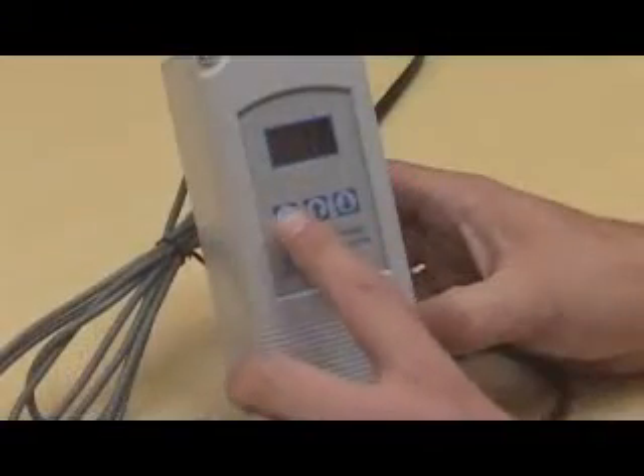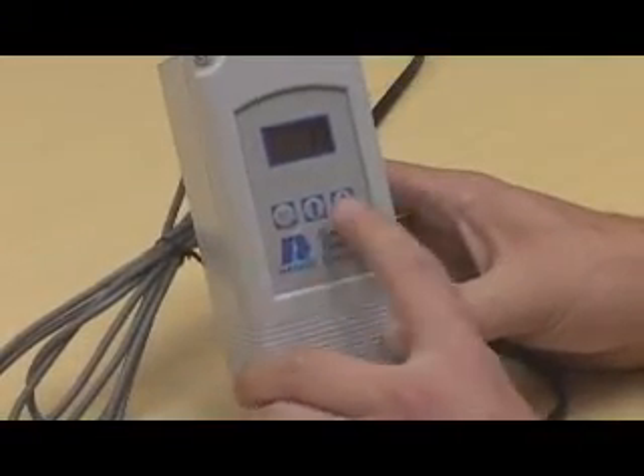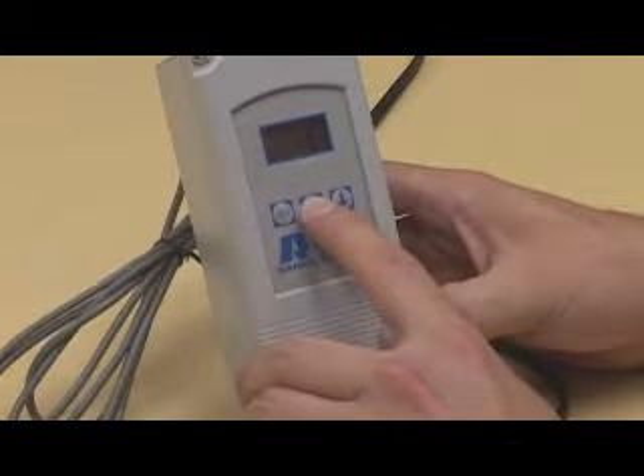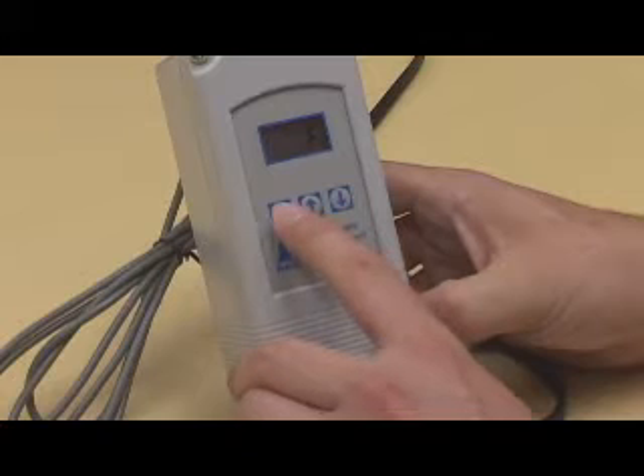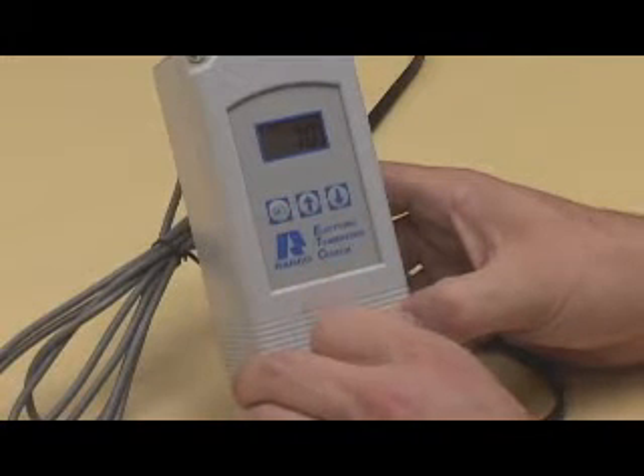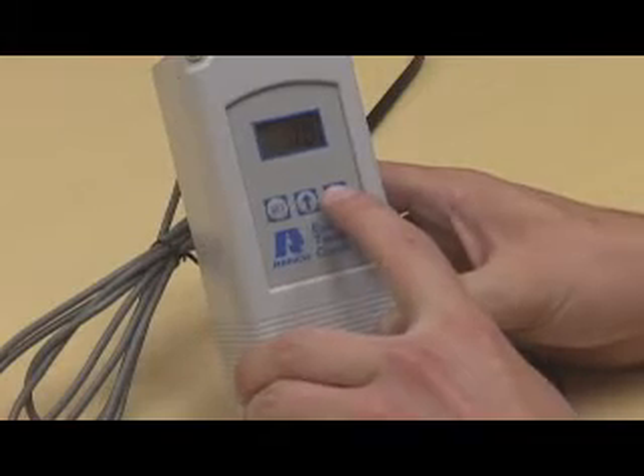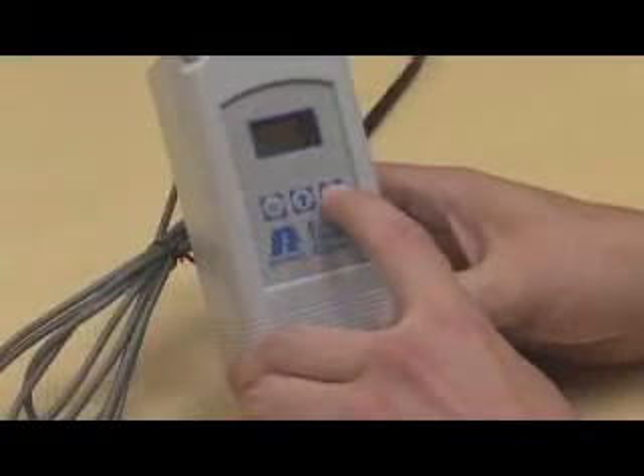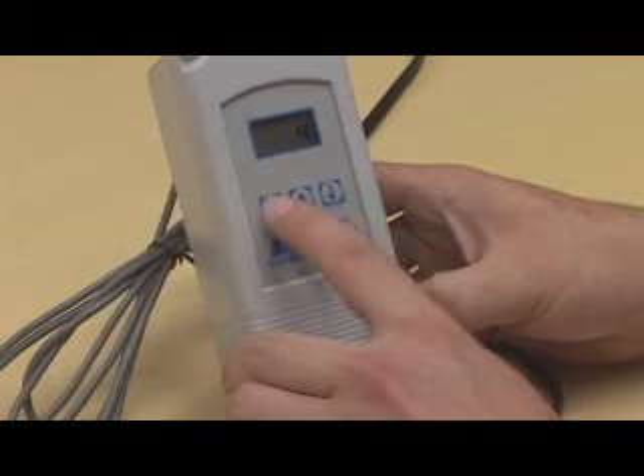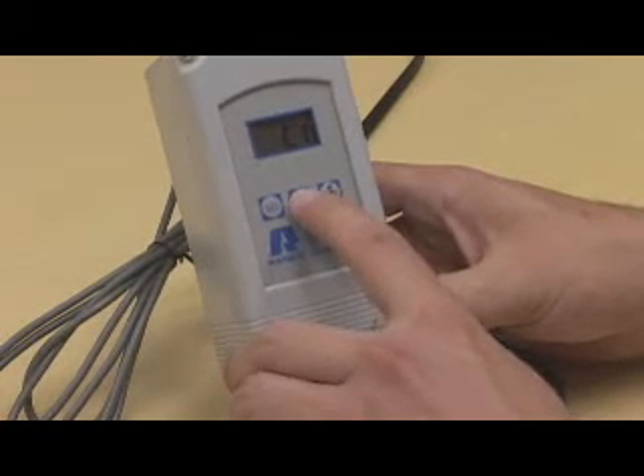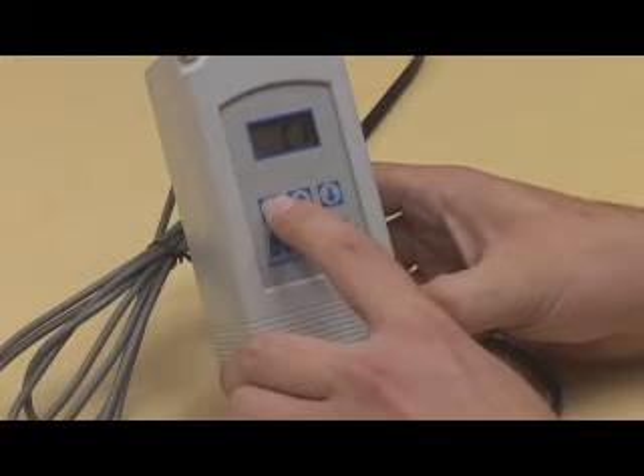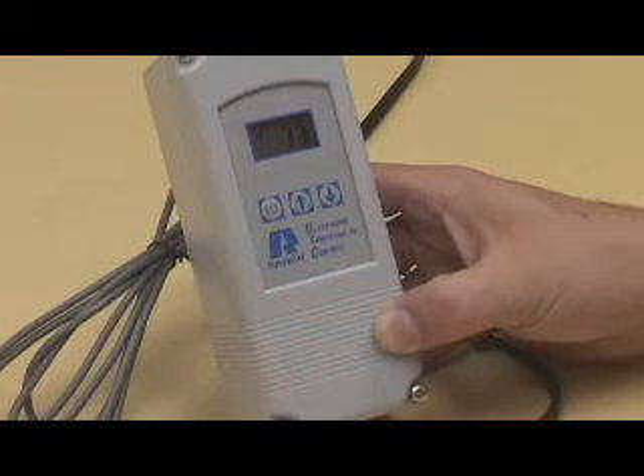Next, you are ready to program the unit. The ETC can be programmed in 4 simple steps using the 3 keys on the face of the control. 1. Press the set key once. Select F for Fahrenheit or C for Celsius using the up and down arrows. 2. The LCD display will show set point S1. Use the arrows to select set point. 3. The LCD display will show differential D1. Use the arrows to select the differential. And finally 4. Select either C1 for cooling mode or H1 for heating mode. Press set one final time to save and initiate the program.